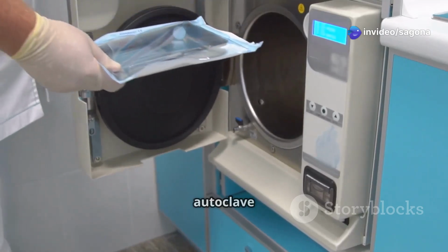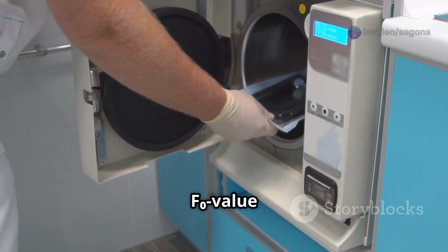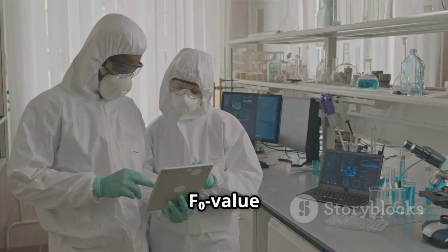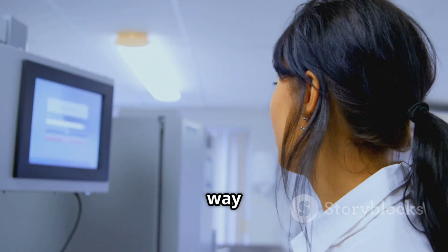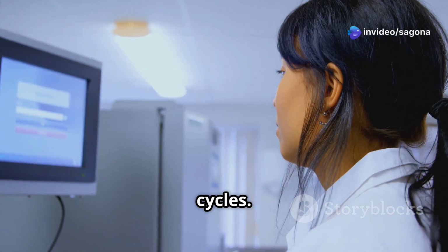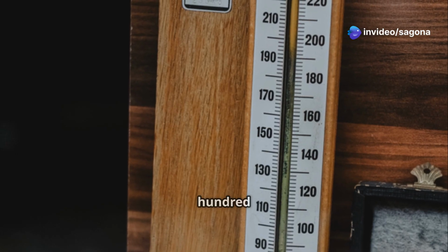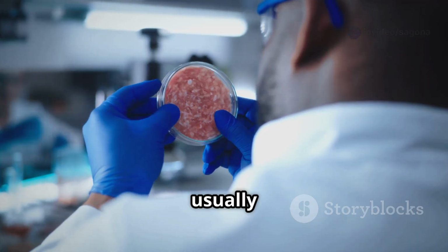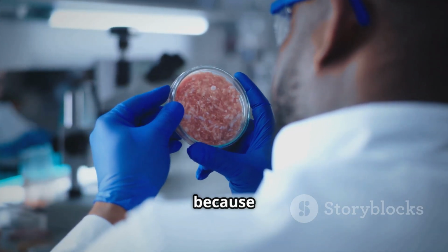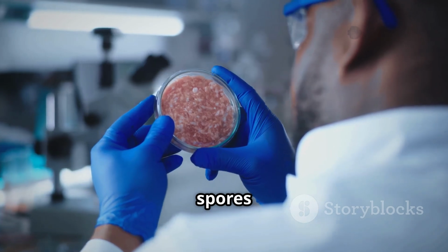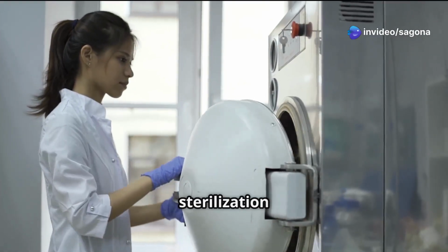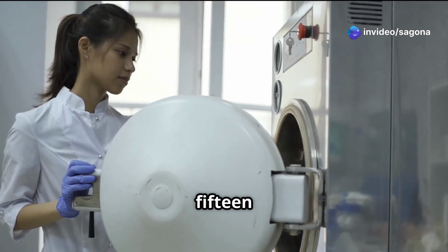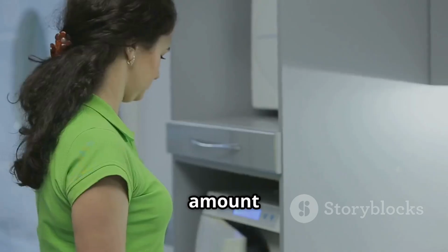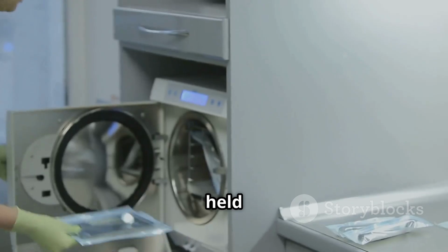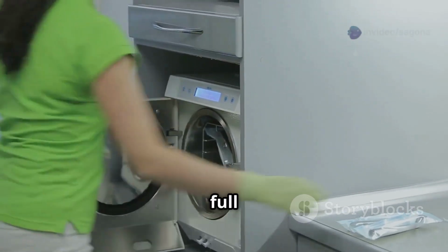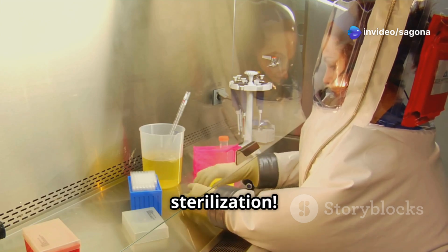So even if the temperature inside the autoclave wiggles up and down a bit, the F0 value adds up all that germ-killing power. The F0 value is super handy because it gives us a standard way to measure and compare different sterilization cycles. The reference temperature is almost always 121 degrees Celsius, and it usually uses a standard Z value of 10 degrees Celsius because this is typical for many of the toughest bacterial spores we need to eliminate. For example, if a sterilization cycle has an F0 value of 15 minutes, it means that the process delivered the same amount of microbial killing as if the items were held exactly at 121 degrees Celsius for a full 15 minutes. It's like a universal yardstick for sterilization.